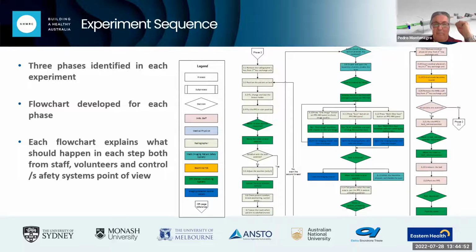By the time the clinical person responsible for the imaging has decided how many images they want to collect, and what is the total mean glandular dose they want to give, we set the Beamline to do that scan. When it is set up, we actually put a phantom into the bed, and we perform a scan as if the patient was there and measure the integrated dose.